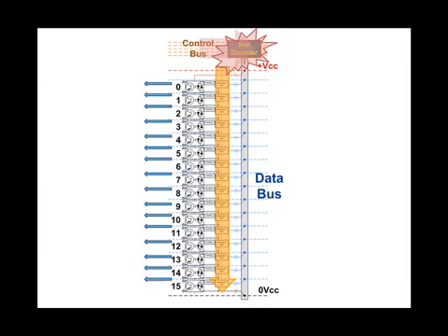During the input image scan, the process is slightly different, but basically the same. In the input image scan, the processor activates the slot of an input module resident in that slot, which allows the state of all 16 input devices to be felt on the 16 conductors of the data bus on the backplane. The processor then reads the 16 states from the data bus into a word in memory assigned to that slot. That is all there is to the activity of I/O modules on the backplane.